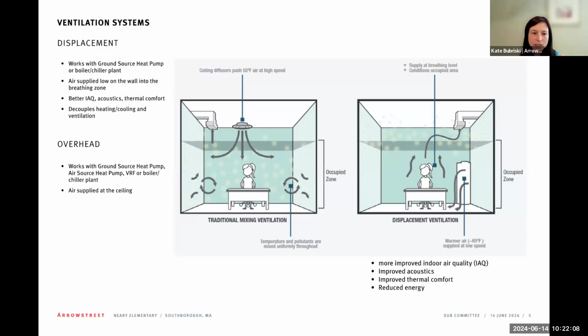Displacement ventilation is supplying air low on the wall in the occupied zone and the breathing zone, and so it can be supplied at a lower velocity. Instead of mixing, it's coming in where you need the ventilation in the breathing zone, and then it's exhausting up high, similar to a traditional mixing system. The exhaust is up high, and basically the temperature of the air sort of stratifies and allows the air quality. Well, both systems will be high air quality because we'll be doing filtration systems.